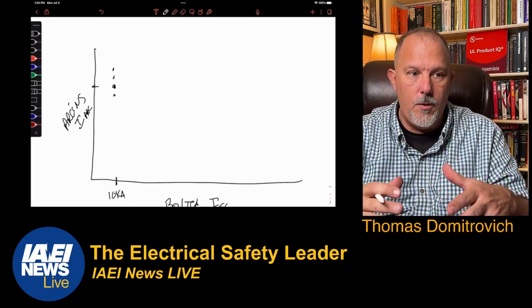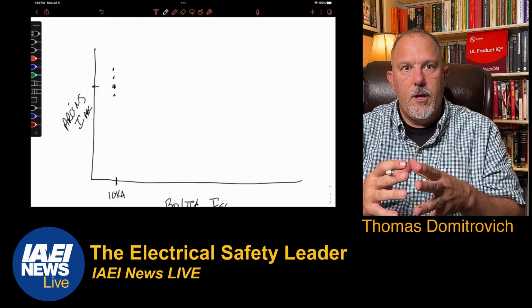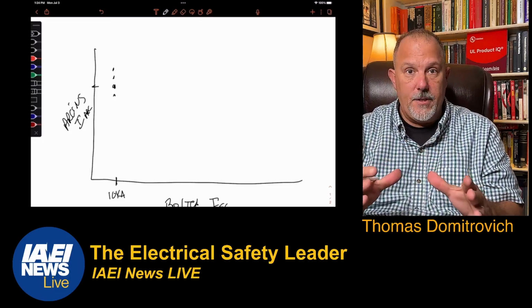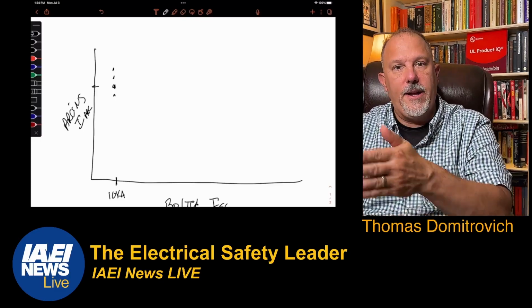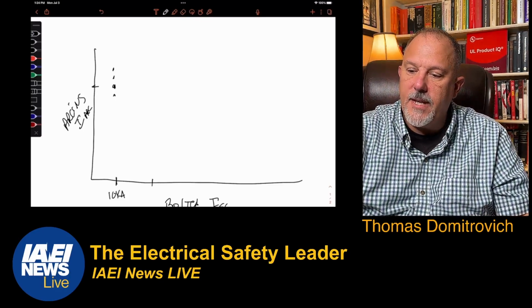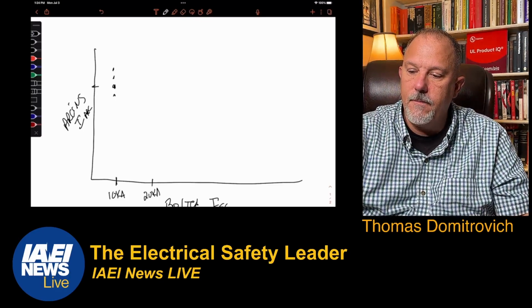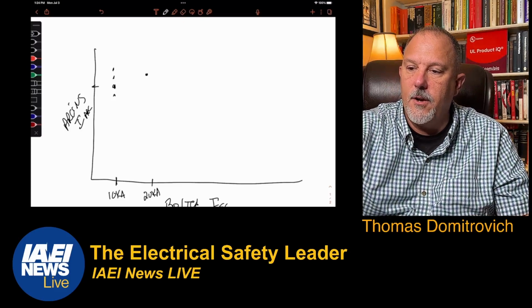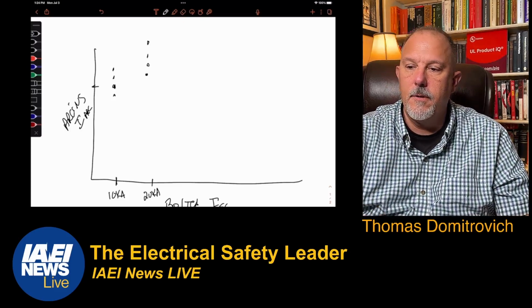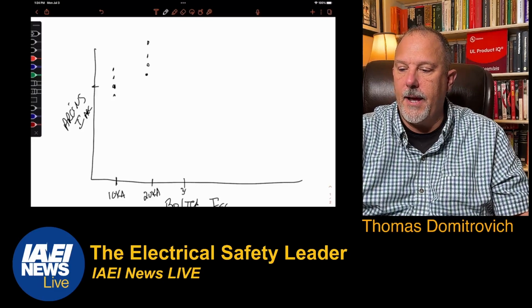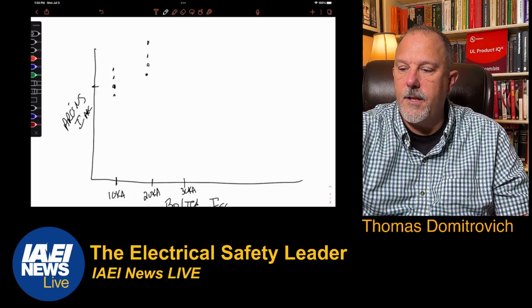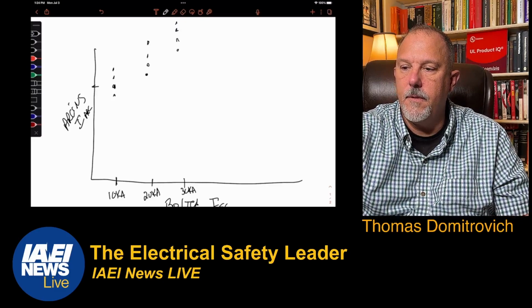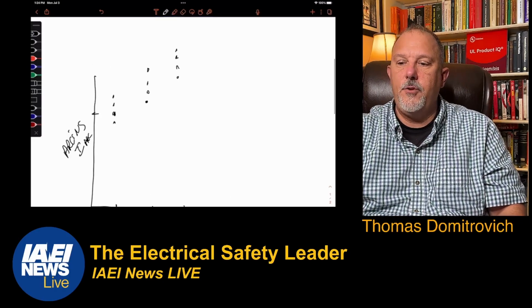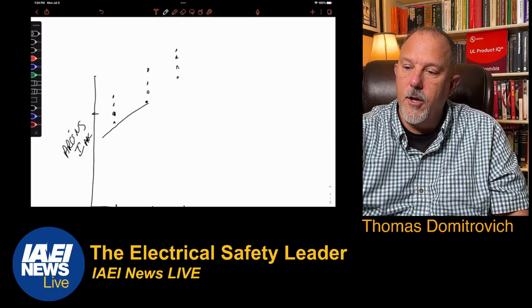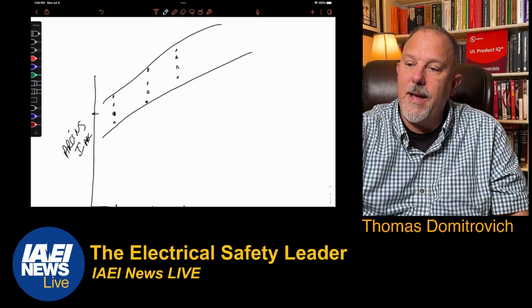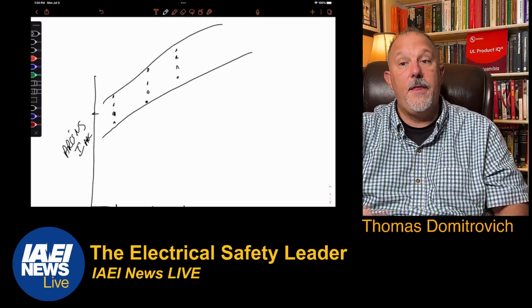Because what we know is that every arc is different. So we have all of these arcing events. And then we say, let's hit it with 20K, and then you'll see the arcing currents go up. And then we hit it with 30K, and you'll see the arcing values go up. Right? So eventually you get a curve. You have a minimum and you have a maximum.